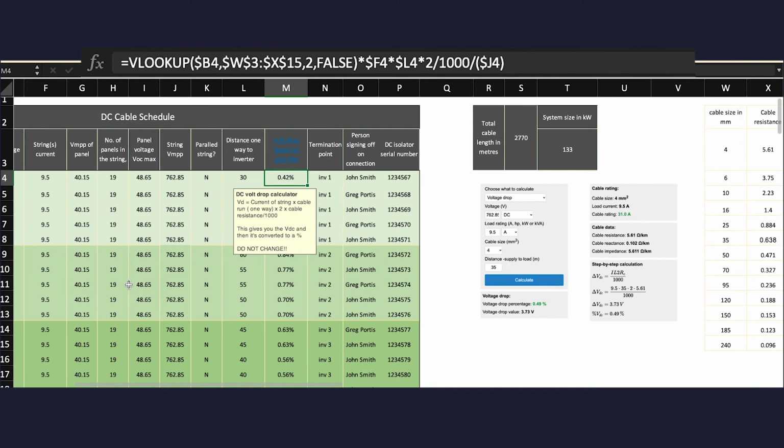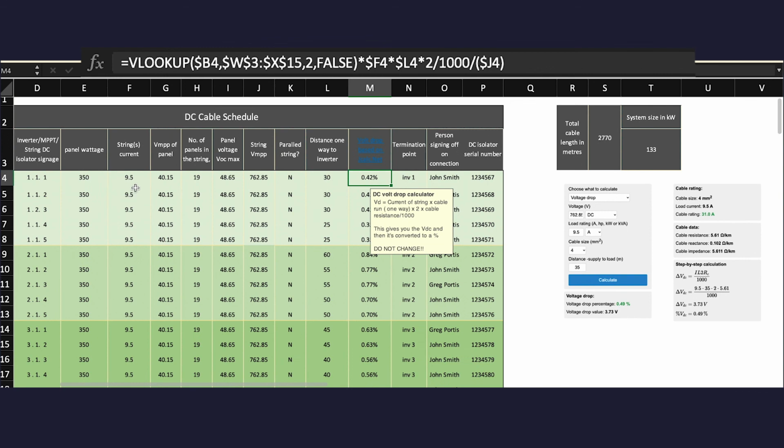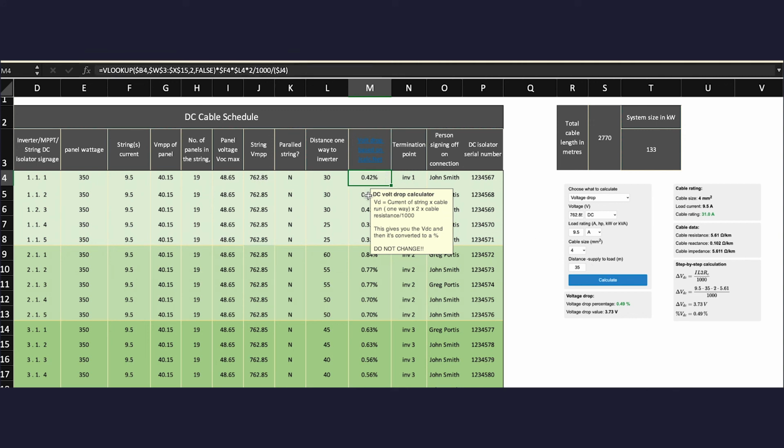It multiplies it by what's in F4, which is the string current, multiplies that by what's in L4, which is the distance, multiplies that by 2 because it's return, divides by 1,000 because we are talking about resistance per kilometre, and then divides again by what's in J4, which is the string voltage at maximum power point, to get a percentage, which in this case is 0.42.